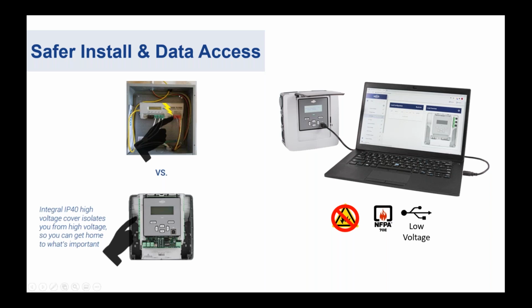There was no cover, there was no safety feature over that terminal block, so you had high voltage right there. So what we did is we made the PCBA frame assembly, the guts of the meter, so that once it snaps into that housing, it's an IP40 high voltage cover. All the high voltage is behind that PCBA frame assembly, and you can't get a finger or a tool in there without removing it with a tool. So it's very safe and isolates the contractor doing the high voltage from getting shocked or being in some sort of unsafe situation. Then you'll have the cover on top of that, which will protect you from any arc flash situations without having to be in an arc flash suit.